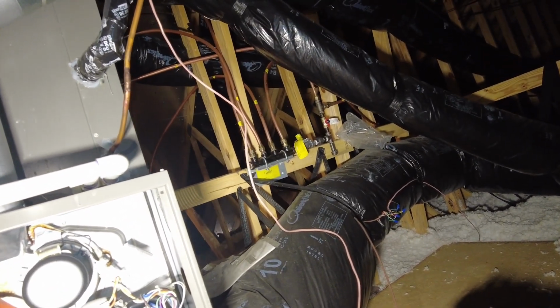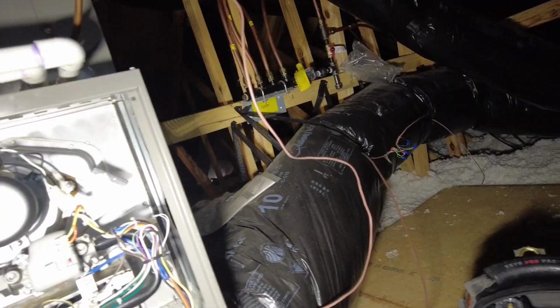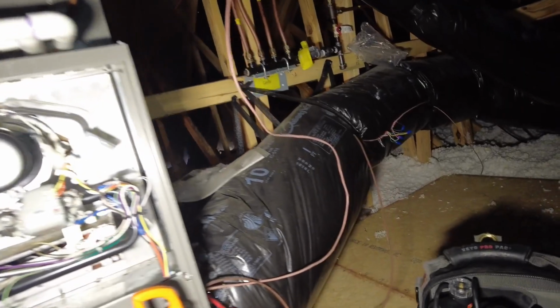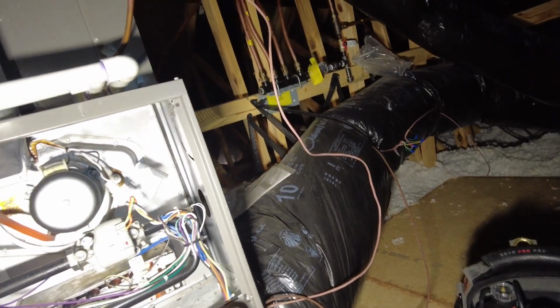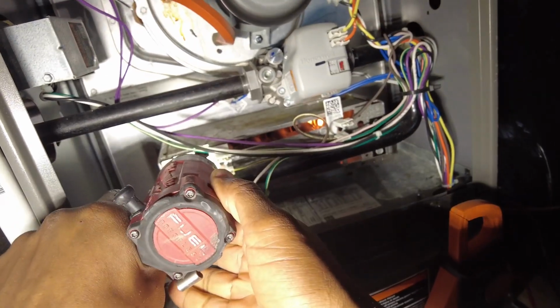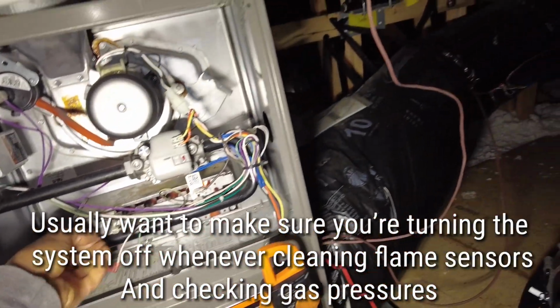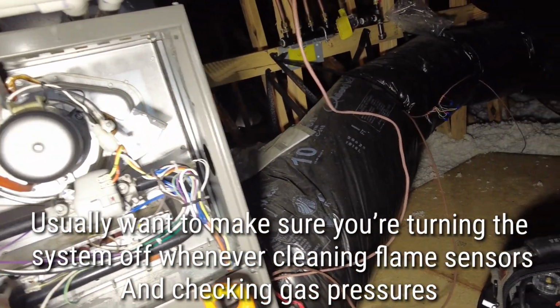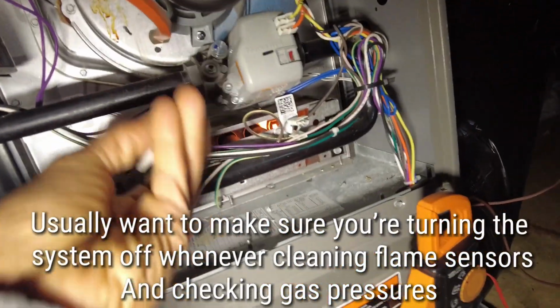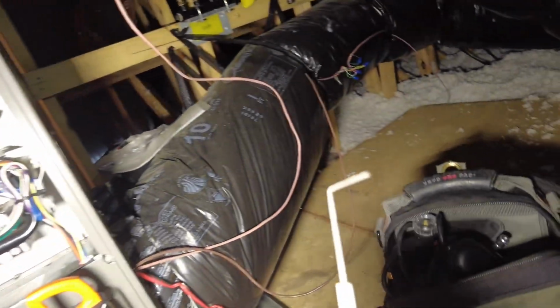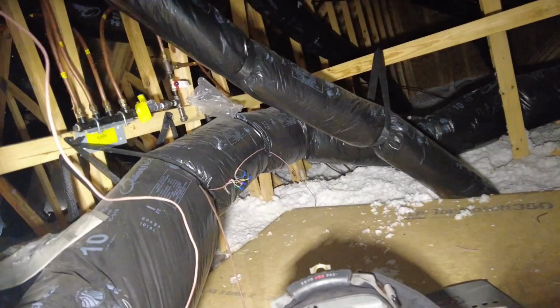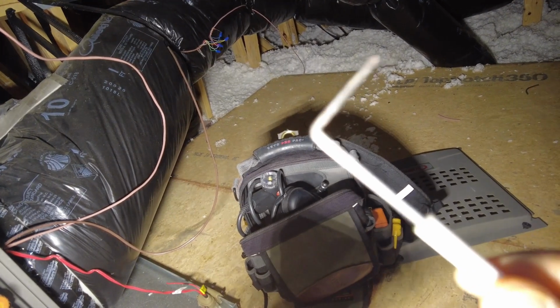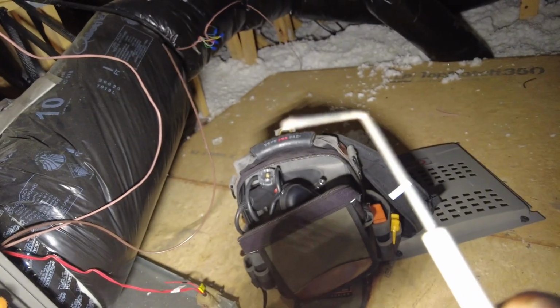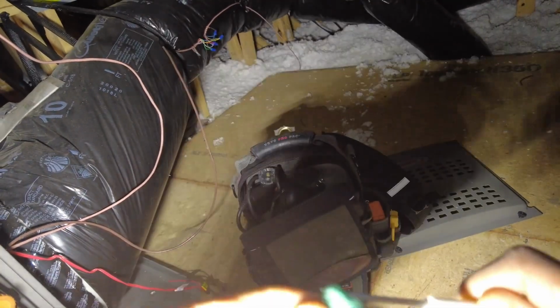We checked everything we need to check other than gas pressures. We're gonna clean that while it's off. And to clean it, you just want to simply clean it. We just want to go ahead and pull that screw out, just one screw usually. This thing just pulls out like such. So there we go. And I just keep this type of Brillo pad on us, okay? But this one actually looks pretty decent. A lot of times you'll see just a bunch of powdery white residue on there, but that's fine.